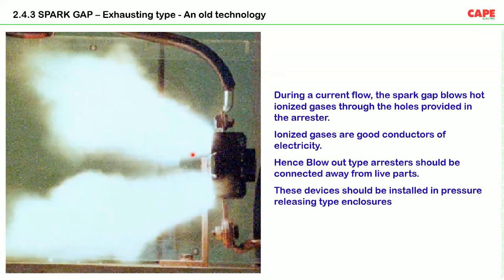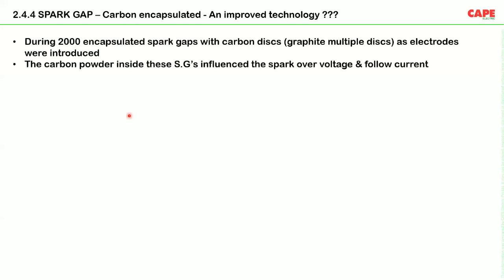You can see some manufacturers who have discontinued such products in their European market still selling in India. Be very careful. Don't use an exhausting type spark gap. It's a very old technology, and if you are connecting this kind of device in your panel board, you have to be very careful. You have to keep these devices away from your conductive parts such as bus bars.